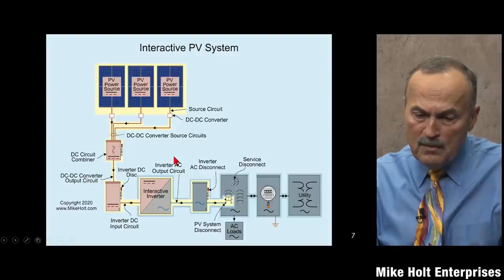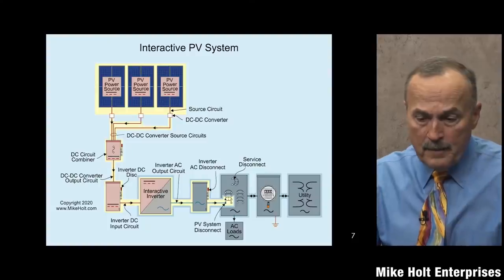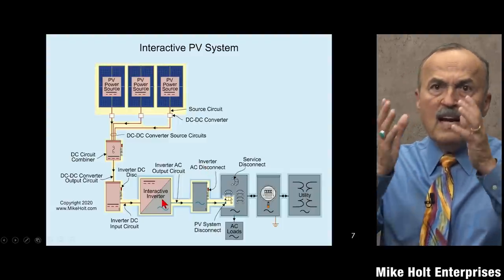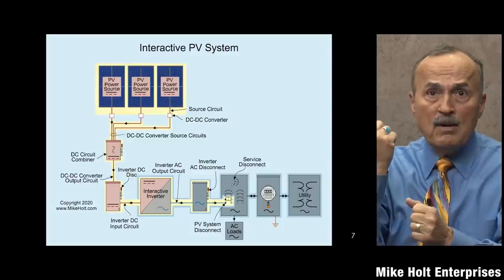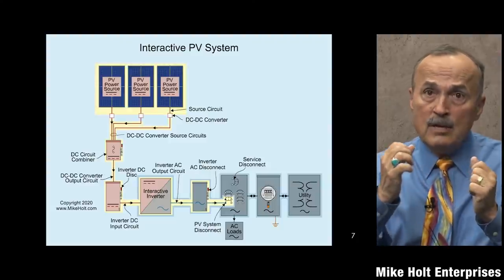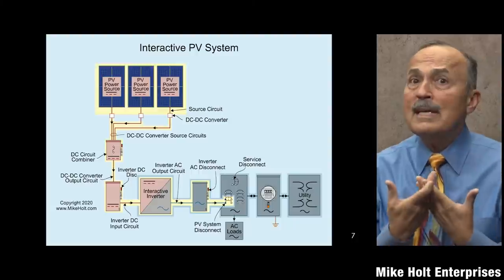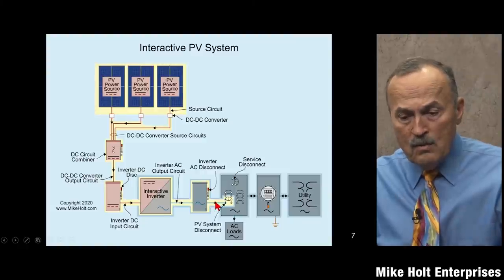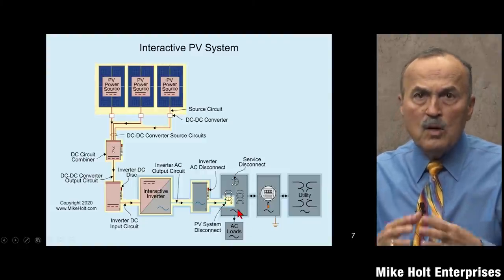What's leaving the inverter is the inverter AC output circuit. The terms are intuitive - DC input, AC output. Then there's a disconnect: the inverter disconnect. If you want to work on the inverter, you have to be able to turn off both the DC input power and the AC power. You need both an AC disconnect and a DC disconnect so you can safely service that equipment.